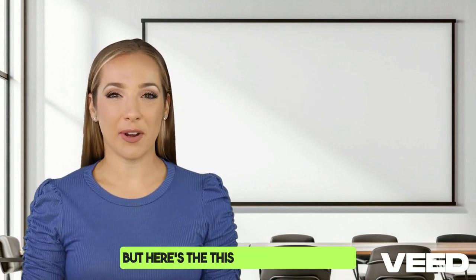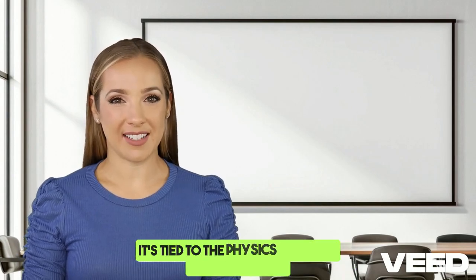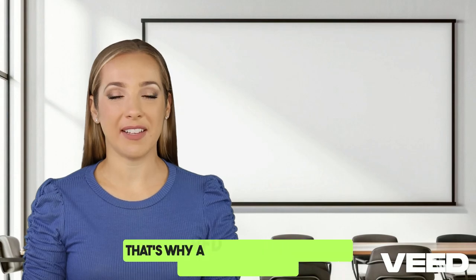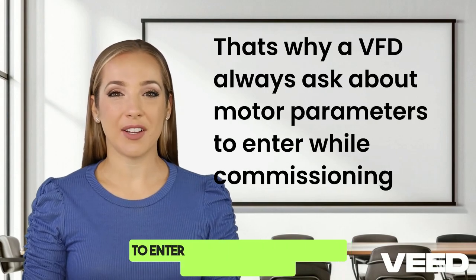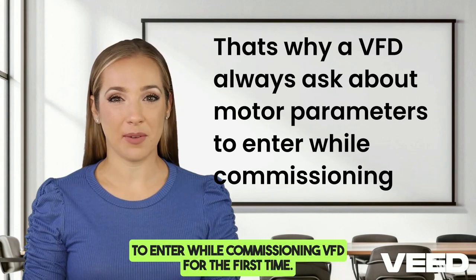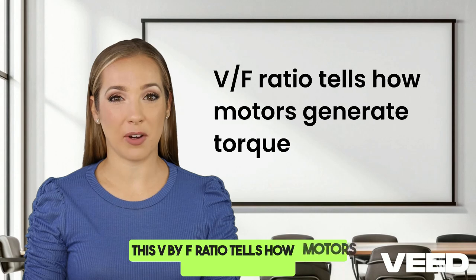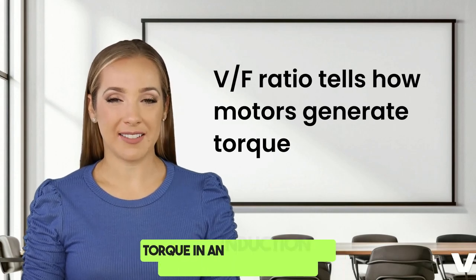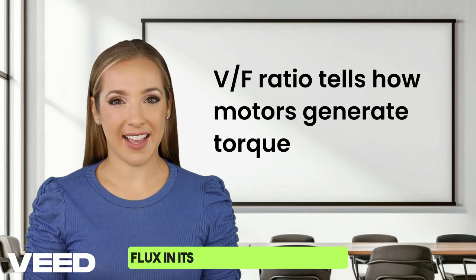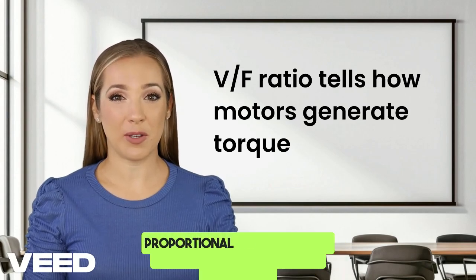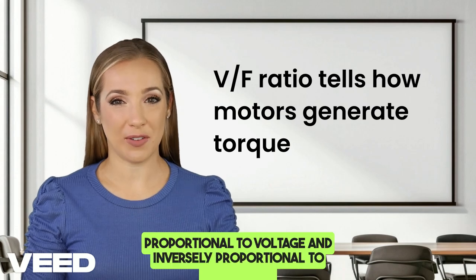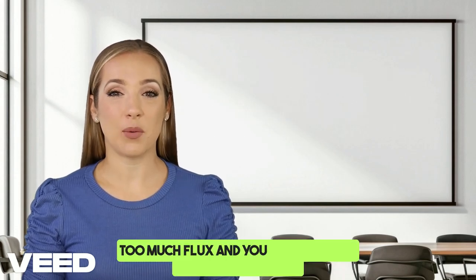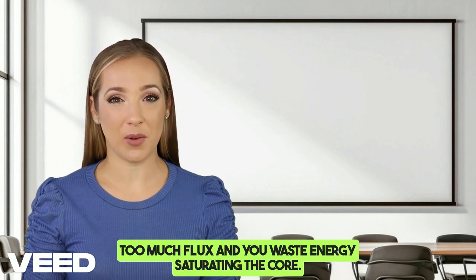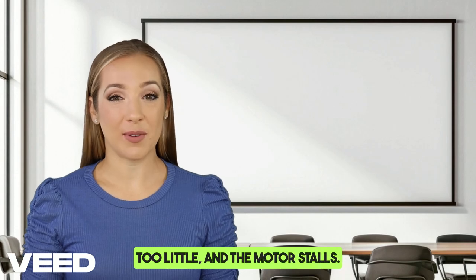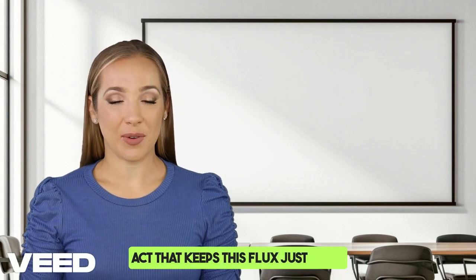But here's the kicker: this ratio isn't random. It's tied to the physics of motor manufacturing. That's why a VFD always asks about motor parameters to enter while commissioning a VFD for the first time. This V by F ratio tells how motors generate torque. Torque in an induction motor depends on the magnetic flux in its air gap, and that flux is proportional to voltage and inversely proportional to frequency. Too much flux and you waste energy saturating the core. Too little, and the motor stalls. The V by F ratio is the balancing act that keeps this flux just right.